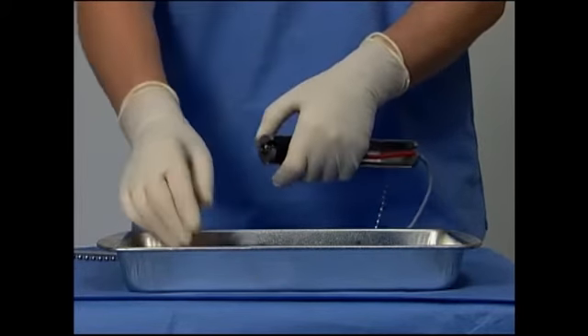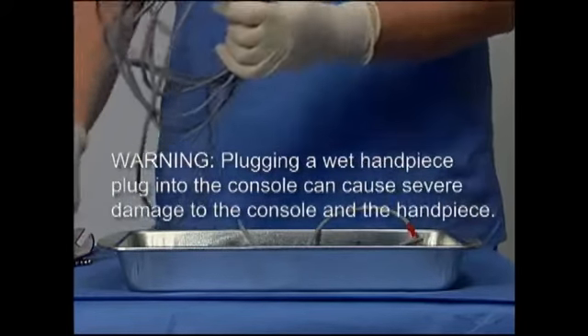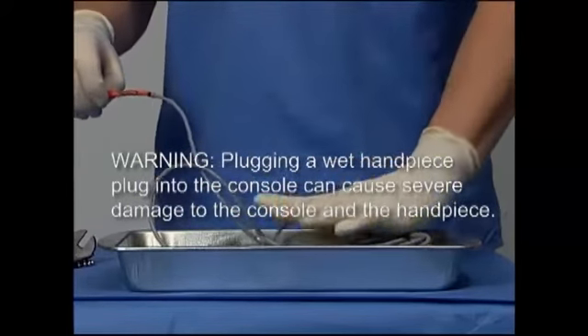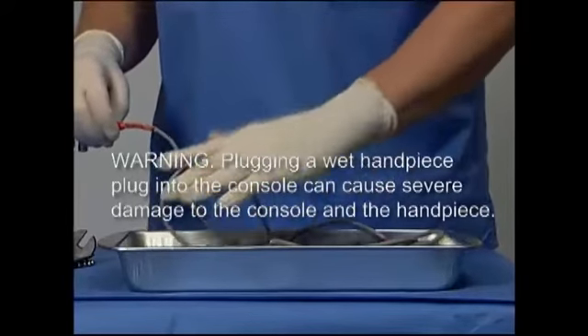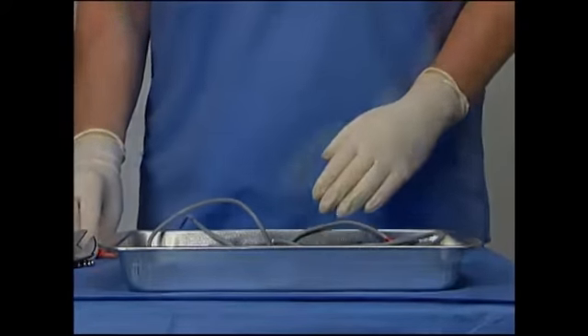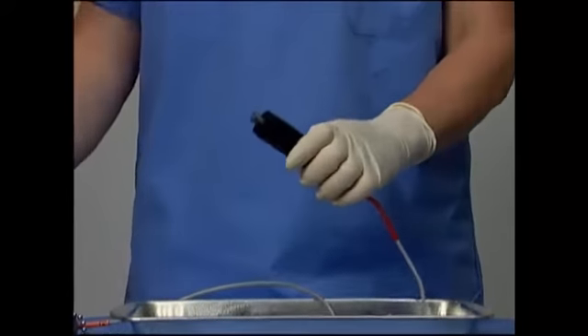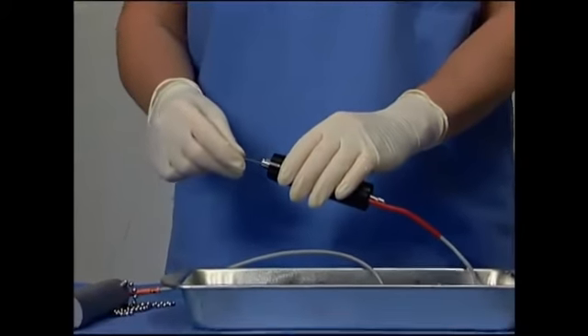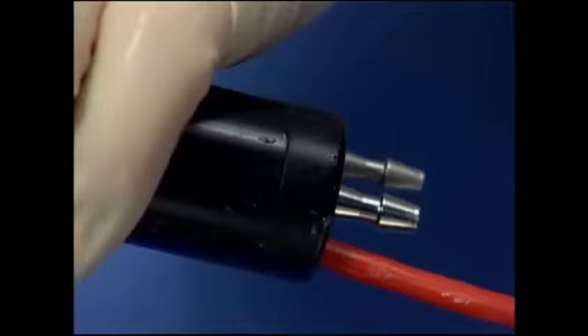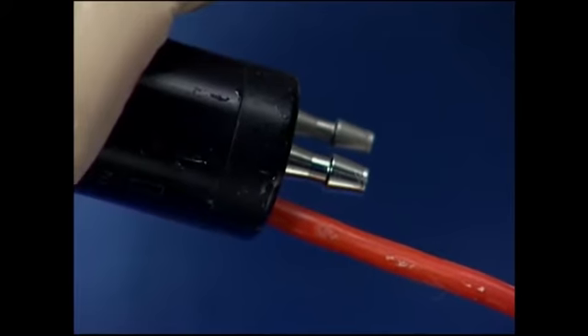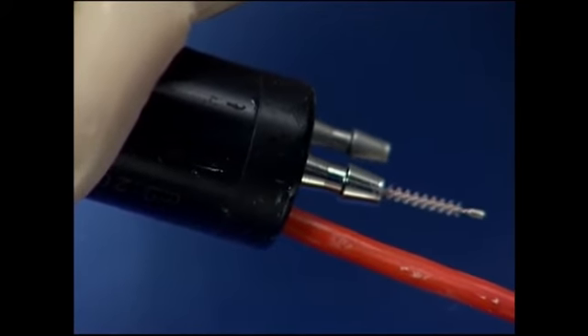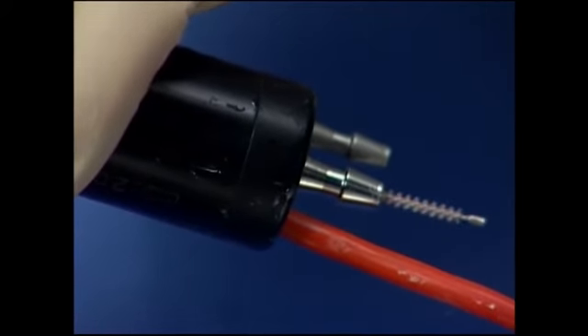Keeping the handpiece plug dry, place the handpiece handle and cord into the cleaning solution. Warning: plugging a wet handpiece plug into the console can cause severe damage to the console and the handpiece. Thoroughly clean the lumens of the disassembled handpiece and parts by inserting the aspiration port brush in the direction of aspiration. Always push the port brush through from the tip end of the handle. Never enter via the rear of the handpiece, as this could result in internal damage.